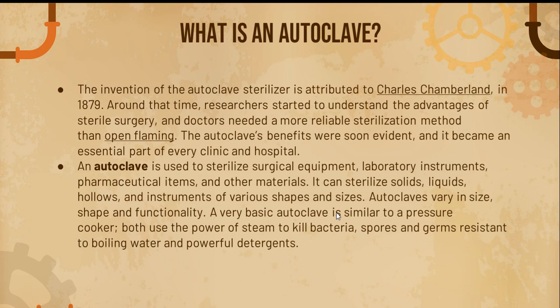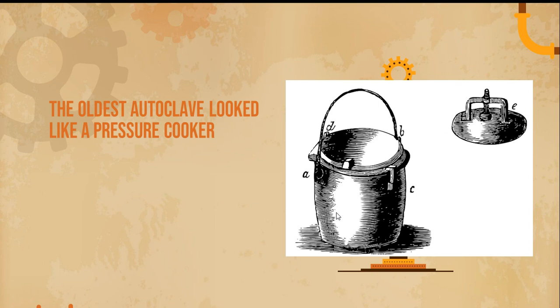An autoclave is used to sterilize surgical equipment, lab instruments, pharmaceutical items, and other materials. It can sterilize solids, liquids, hollows, and instruments of various shapes and sizes. Autoclaves vary in size, shape, and functionality. A very basic autoclave is similar to a pressure cooker. Both use the power of steam to kill bacteria, spores, and germs resistant to boiling water and powerful detergents. So over here we have the oldest autoclave, which looked almost very similar to a pressure cooker. And here we have a modern autoclave.